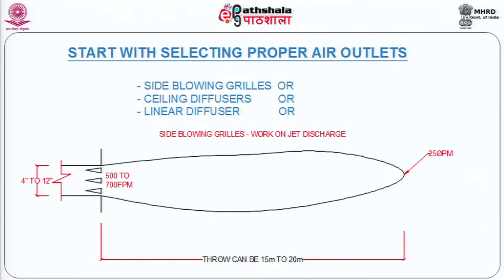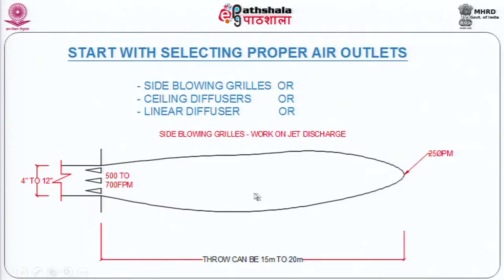One is the sidewall grill, which is very commonly seen. A sidewall grill works on a principle of jet displacement of air and is one of the most difficult grills to place for a draft-free requirement, because the velocities that come out are very high and they are sort of split. It is not like a laser, where it runs in a single straight line. It basically runs as a jet. So it is very difficult to exclude the jet from the occupied area.